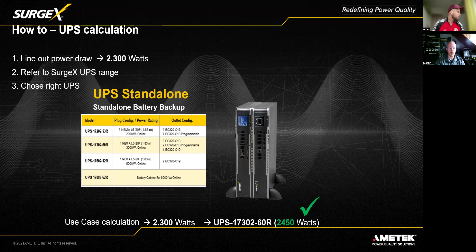Then we would need to cover the runtime, so we'd double check the runtime on 2300 watts, or if we need additional battery cabinets. We also supply battery cabinets with our UPSs to extend the runtime, but that's not changing the maximum power. That's not possible — I need to exchange the UPS.